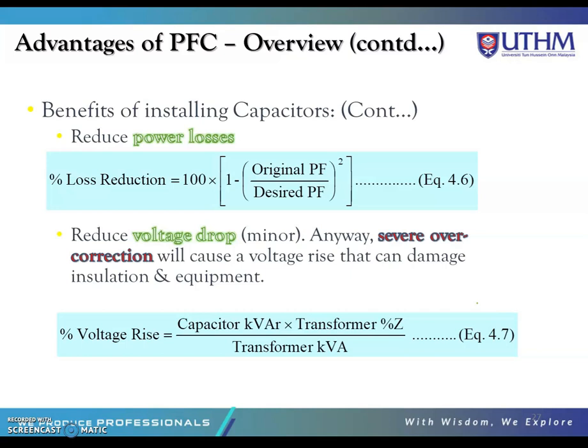Capacitors also reduce power losses. The percentage of loss reduction is calculated as: 100 × [1 − (original power factor / desired power factor)²]. We must also monitor voltage because severe overcorrection can cause a voltage rise that damages insulation and equipment. The percentage voltage rise is calculated as: (capacitor kVAR × transformer percentage Z) / transformer kVA.